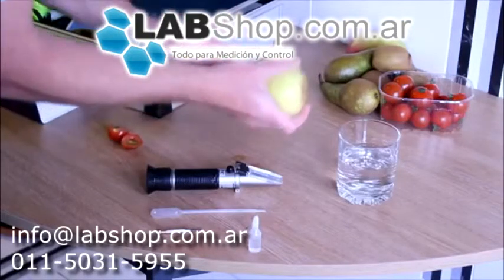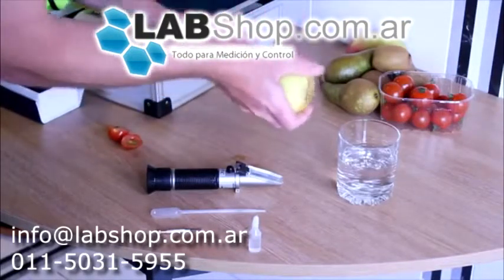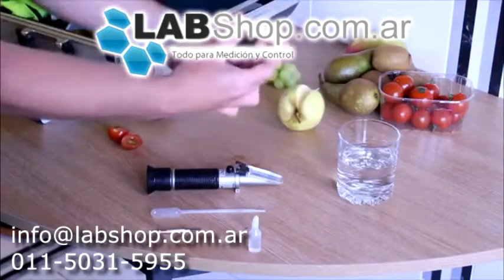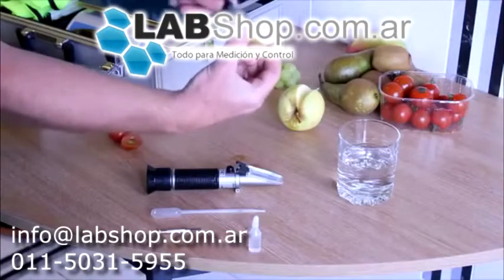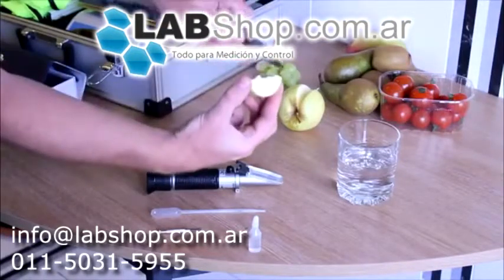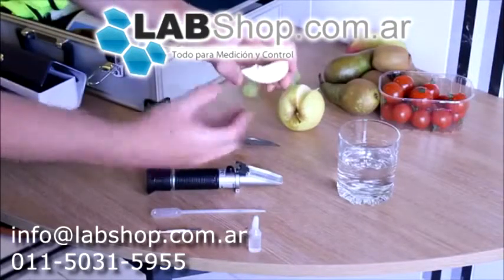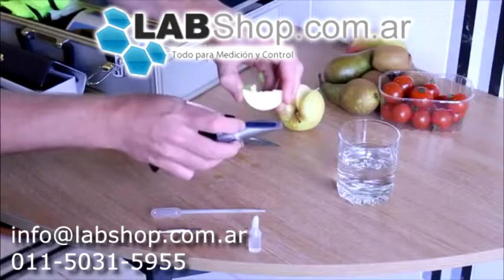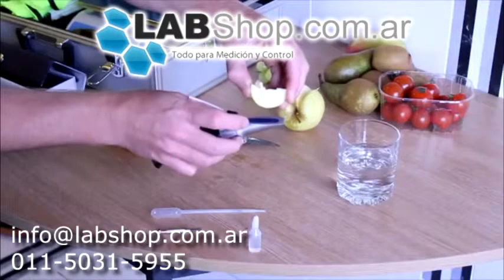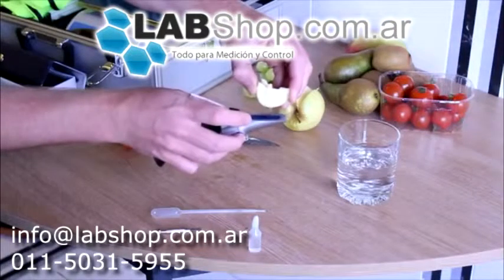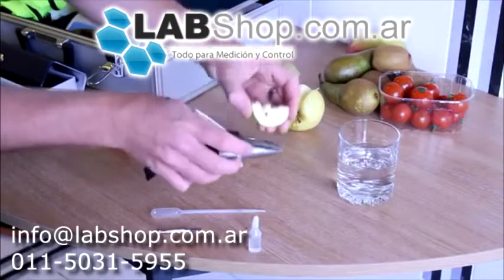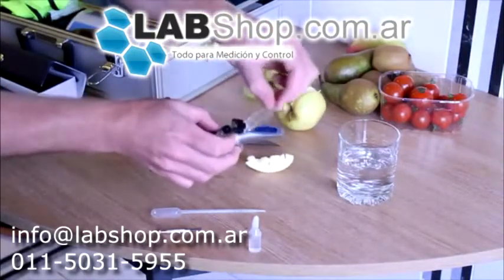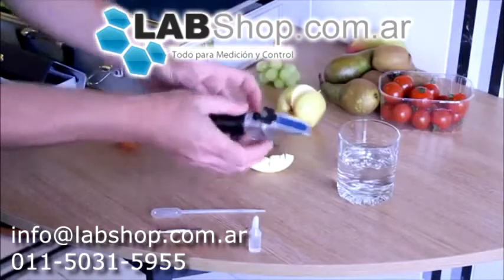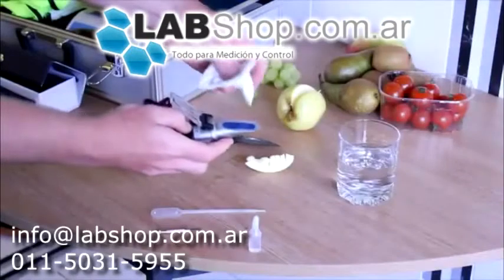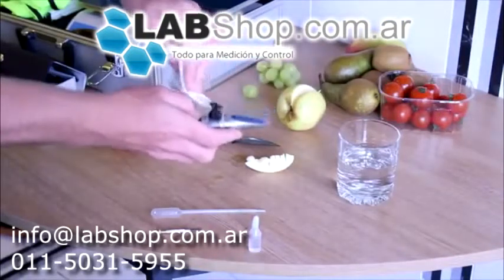In the case of apples, and similarly pears, we recommend taking a wedge shape of fruit rather than slicing the whole fruit in half. You can then use your knife to score your wedge several times, which will make it easier to squeeze some of the juice onto the glass plate of the refractometer in the same way that we did with the cherry tomatoes. Once again, you are aiming to get a nice even covering of juice over the glass plate. Lay the plastic cover over the plate and look through the reverse to take your reading using the gauge. In this case, higher than the tomatoes, more in the region of around 14–15%. Before once again cleaning your equipment thoroughly.